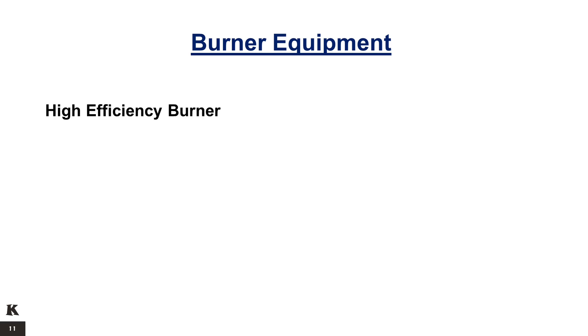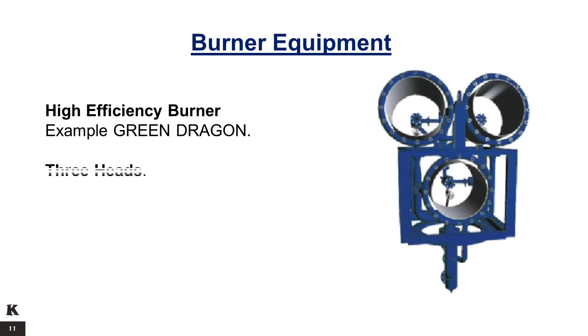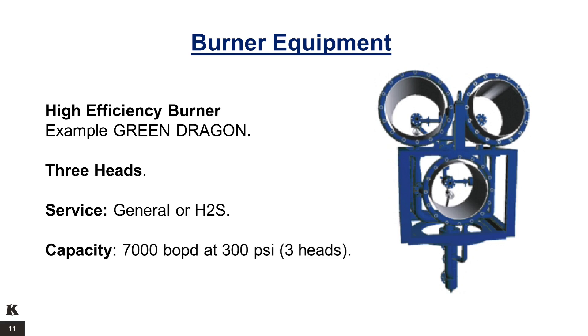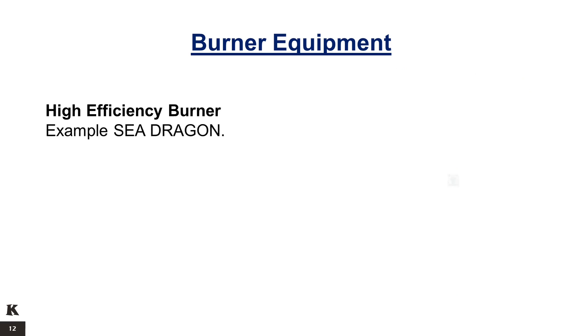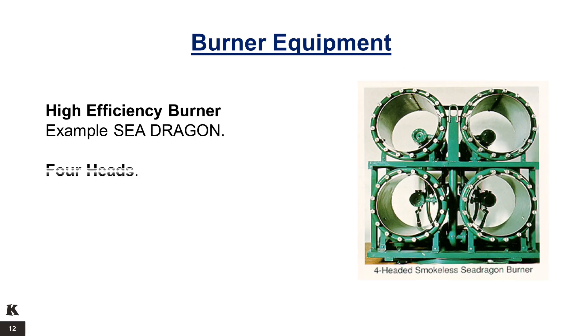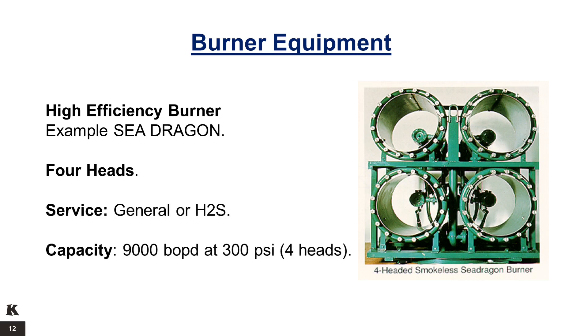High-Efficiency Burner. Example: the Green Dragon. It is a three-headed burner used for general or H2S service. Its maximum capacity is 7,000 barrels of oil per day at 300 PSI with three heads used. The Sea Dragon is a four-headed burner also used for general or H2S service, with a maximum capacity of 9,000 barrels of oil per day at 300 PSI with four heads used.